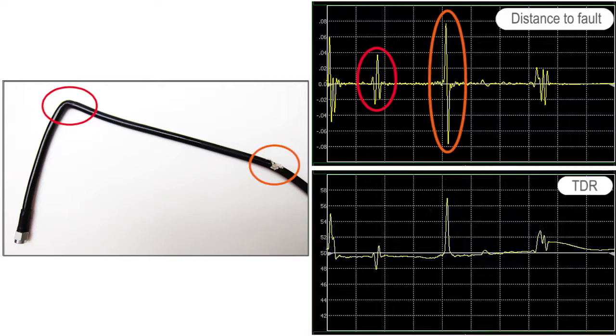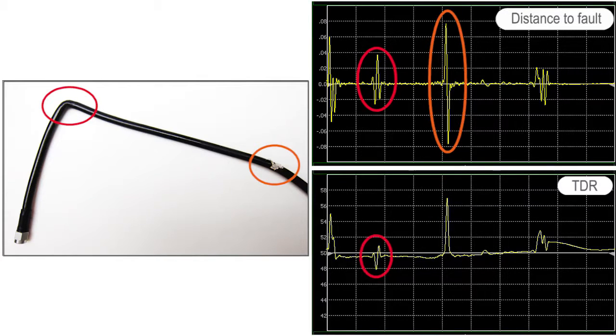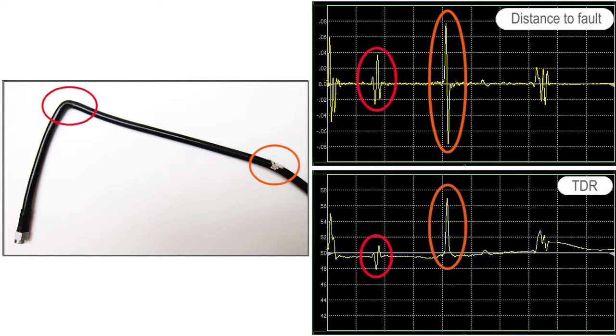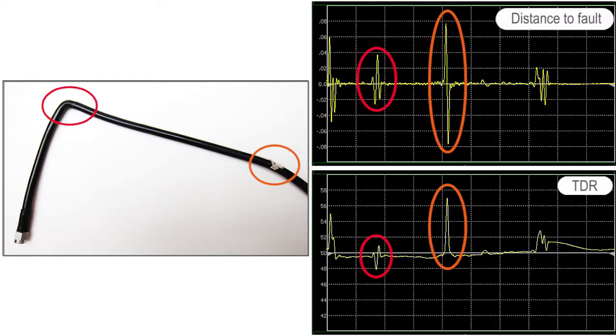The distance to fault function shows exactly where the faults are, and the TDR function shows the bend fault as capacitive and the nick as inductive, helping the technician figure out what the faults are.